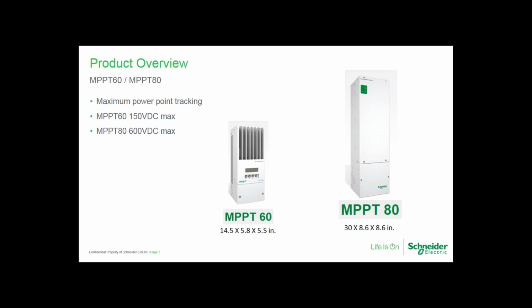MPPT-60 was actually released with the legacy model back in 2007. So it's virtually unchanged in its design. It's proved to be very reliable and robust. The MPPT-80 was released around 2012. So incorporating the high voltage controller did require implementation of a fan. But yeah, that's the main difference between the two, is the 60 amp model is passively cooled, the 80 amp model is actively cooled. Good question.